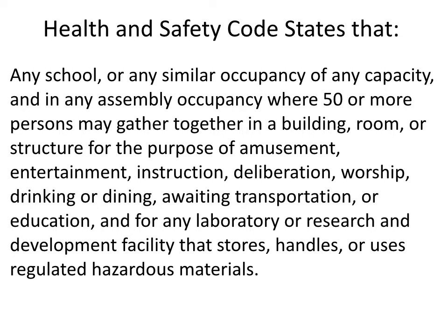If it's somewhere where you get training and it's 50 or more people, if it's a place where you worship, a church, 50 or more people, any restaurant. So think about the In-N-Out that you like to go to, or the Starbucks. Is it 50 or more? Then it's an assembly. If it's 49 or less, then it's just considered a business and it's not under the state fire marshal's authority. So we'll talk about that next week.